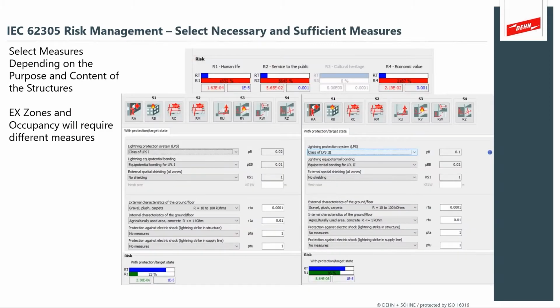So when we look at the risk analysis, we always want to focus on necessary and sufficient measures. We don't want to go overboard, but you need to pay a lot of attention. You'll have structures that have EX zone, explosive zones, and you'll have different levels of occupancy at the control systems, at the administration buildings on these sites. So in an example like this, you can select enough of a lightning protection system, an LPL class 3, that reduces the risk below the tolerable threshold. But you can also be a little bit overboard if you select an LPL 1 type system.